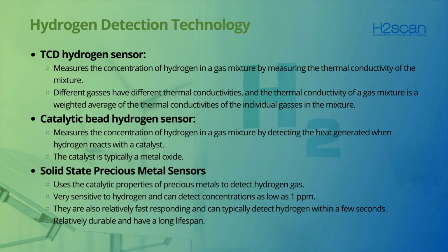Selecting a hydrogen sensor has a lot to do with which application you're going to put it into and the type of properties and responses that you require from the sensor. So the first one I want to address is the TCD hydrogen sensor. TCD stands for thermal conductivity detector. However, TCDs are not very sensitive typically. They can detect concentrations from 100% down to about 100 ppm. They work by comparing the thermal conductivities of two gas flows, the pure carrier, which is the reference, and then the sample. So different gases have different thermal conductivities, and the thermal conductivity of a gas mixture is a weighted average of the thermal conductivities of the individual gases in the mixture.